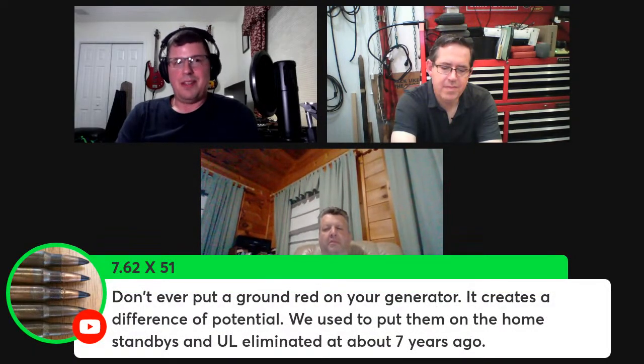I don't think that's what he's asking here, just whether your generator has to have its own ground rod. Well, you not only need an 8-foot ground rod here—we're talking in the United States—an NEC ground rod is 8 feet, and that's going to go to your main panel. If you have a home standby or automatic standby generator, most townships and cities will still require a separate ground rod installed next to the generator. Even the home standby, depending on your setup, may not have internal bonding between neutral and ground; that's usually done through the generator panel, or it could be done at the main panel. So it really depends on your setup, it's not one size fits all.